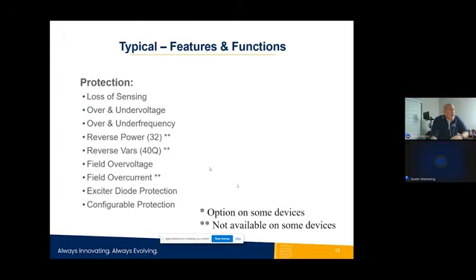And then you've got other protection: over and under voltage, frequency, reverse power, reverse VARs. These are used a lot in motor application. Field over voltage, field over current. Sometimes it's a protection, sometimes a permissive to do something else. And then for brushless applications, you've got your exciter diode protection. That's basically looking at the ripple frequency of the field, and can determine if one of those diodes in the brushless exciter has opened or shorted.